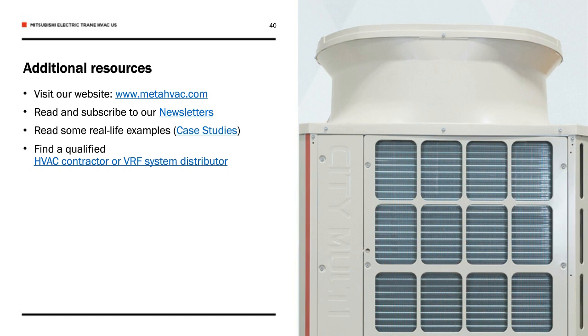It has a feel for what systems and what indoor units are attached to the system, how hard they're working, how fast their fan is running, how wide open their linear expansion valve is. And it takes that information and essentially apportions a percentage of the work being done mechanically within the system. Then it takes that apportionment value and, in concert with an energy meter attached to the outdoor unit and its power feed, it apportions an electrical use to every system or every group of systems within a building.